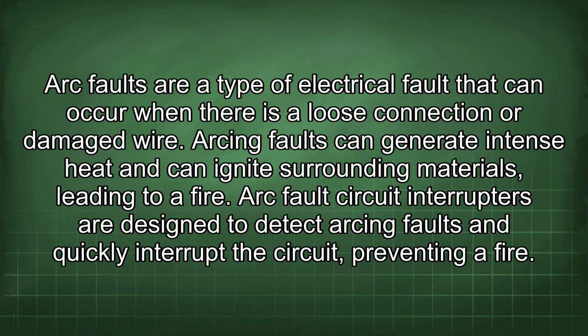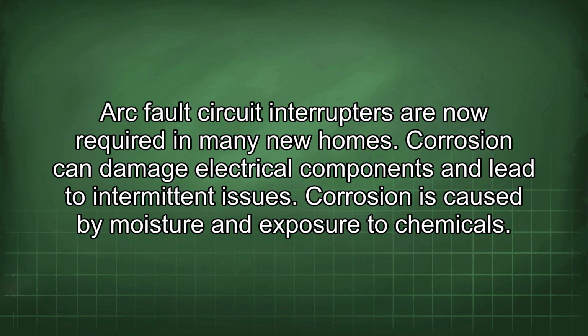Arc faults are a type of electrical fault that can occur when there is a loose connection or damaged wire. Arcing faults can generate intense heat and can ignite surrounding materials, leading to a fire. Arc fault circuit interrupters are designed to detect arcing faults and quickly interrupt the circuit, preventing a fire. Arc fault circuit interrupters are now required in many new homes.